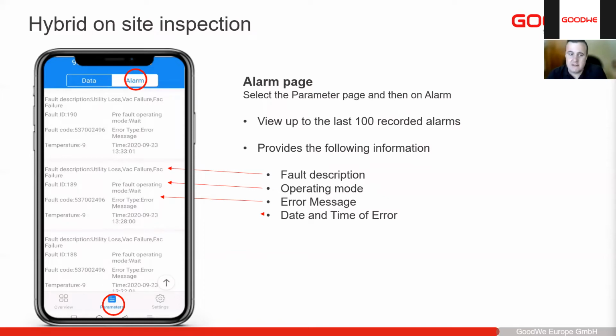So yeah, you'll get a lot of information. What's the fault description? As you'll see in this one, the fault description has 3 different faults: utility loss, VAC failure, and FAC failure. Essentially, the utility is off. There's no voltage, there's no frequency. Then there's the operating mode. Is it in wait mode? Is it in normal mode? Or is it in fault mode?